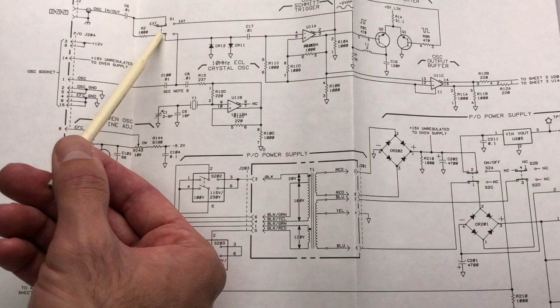This is also a good time to point out the safety capacitors that I just replaced because they're right here on the schematic. All right, so I'll explain what's going on with this circuit and why these need to be safety rated capacitors. So we can see right here we have the AC line coming into the instrument. The top right here is the hot AC line. The middle is earth or chassis ground, which is denoted by that symbol. That's the connection to the chassis ground. And then the bottom right here is neutral.